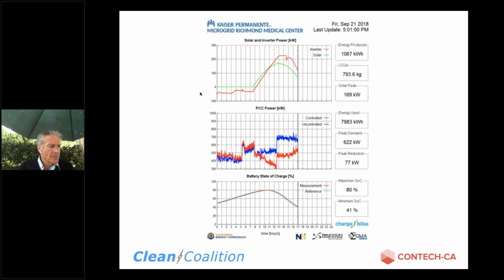And for the first question, actually the controller kind of makes the determination. So it would be shared in the morning, and actually you can see from John's graphic, this top slide, the green line represents the solar production. The red line represents what the inverter is currently doing, the inverter deploying the energy into the building. So you can see it kind of follows that curve, but then also picks up where it's higher than the green line there. That's actually pulling from the storage. So it does both. Some of the solar goes into the building immediately, and some goes into the battery. It's kind of shared. It's based on economics.